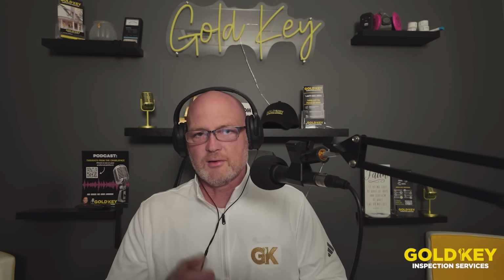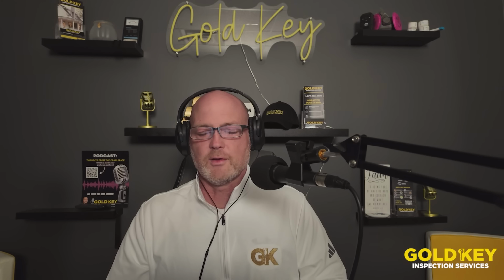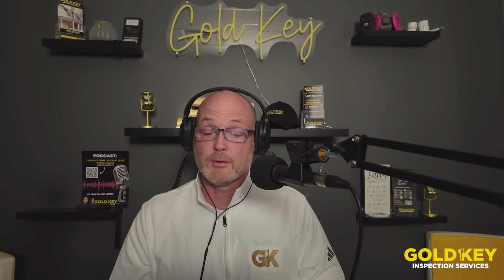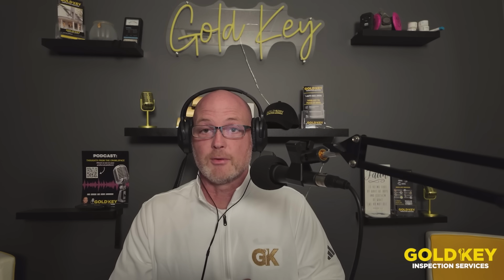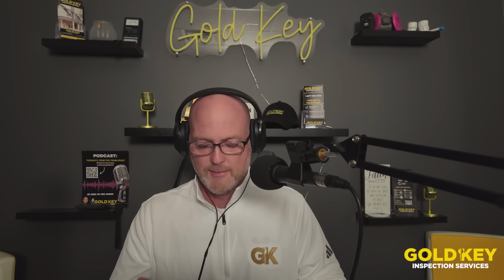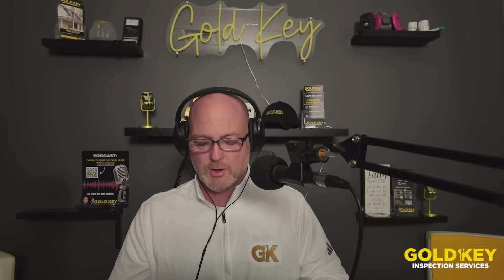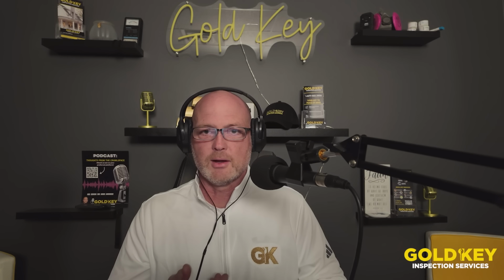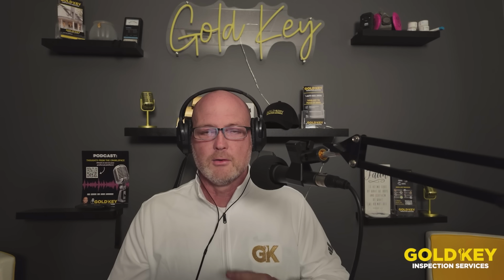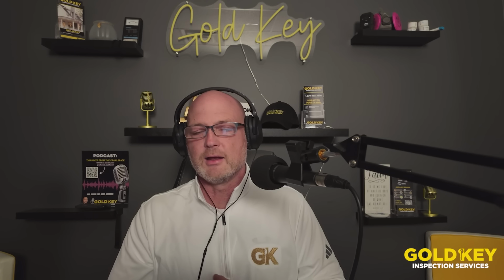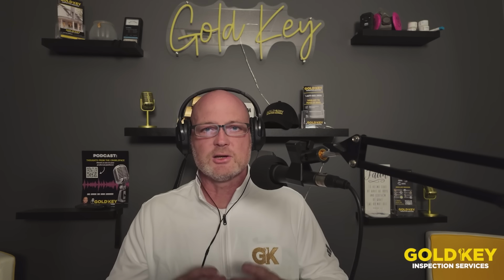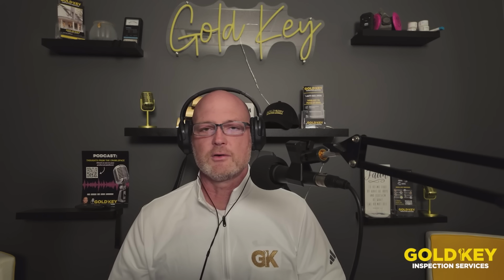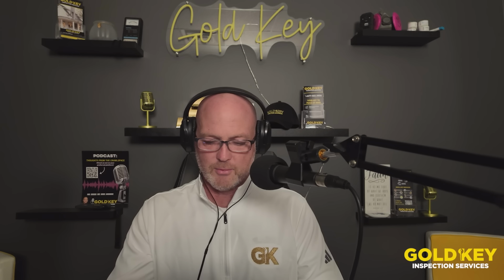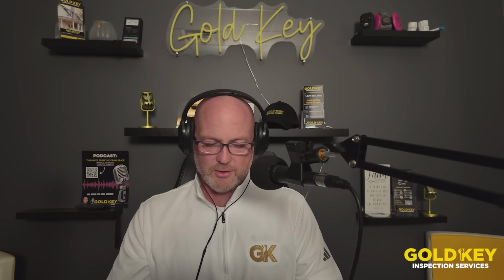So if you're buying a house and it's in the winter, it's just one of the unfortunate realities. We're not going to be able to check the air conditioner for proper function. Now, we're going to look at it. We're going to make sure it's clean. We're going to make sure it has a disconnect. We're going to make sure the condensation line is good. We're going to make sure the filter dryer line is in good shape. We're going to make sure a lot of things are good. We just can't operate it. So there's where you would refer to the seller's disclosure to get more information on that.